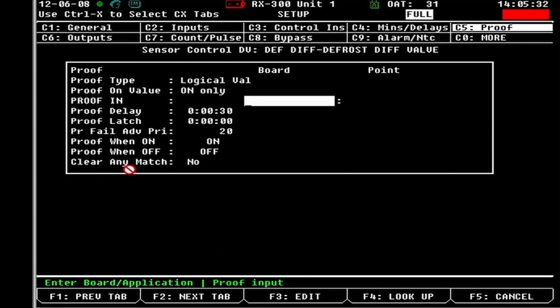So then you also have proof fail, proof latch, proof delay. You have proof when on, proof when off, clear, any, match, yes, no, proof priority. So all that's in here. Not something you use a whole lot. I mean, you could use it on some defrost stuff. I mean, don't use a ton of digital sensor controls. They have their place, and not a whole lot of proof stuff done in them.